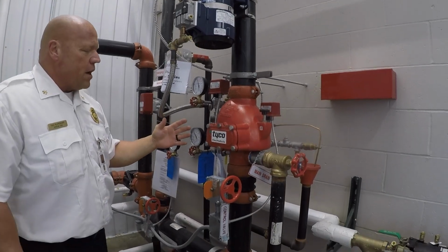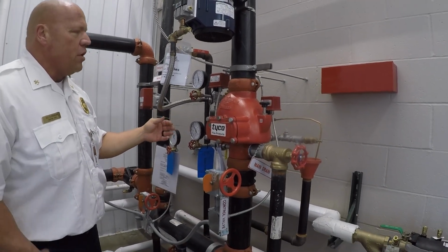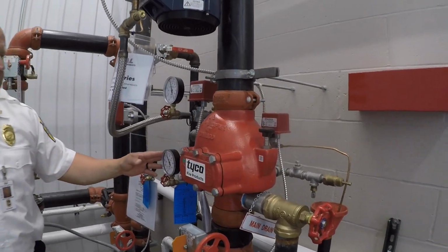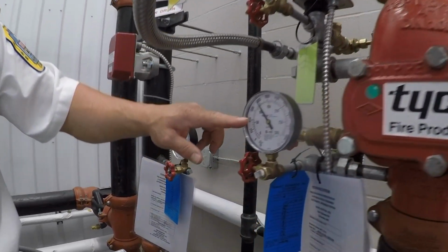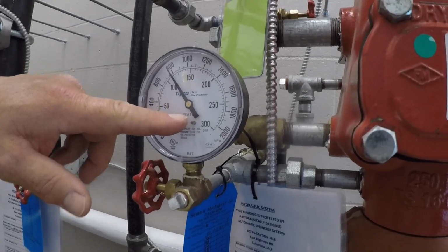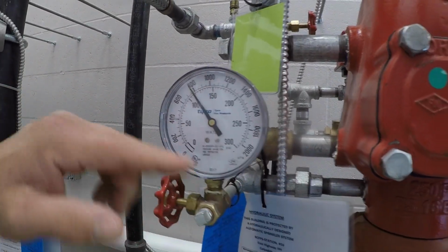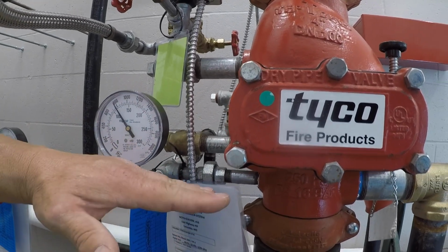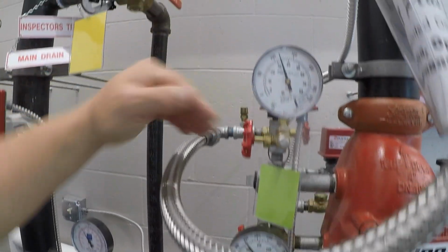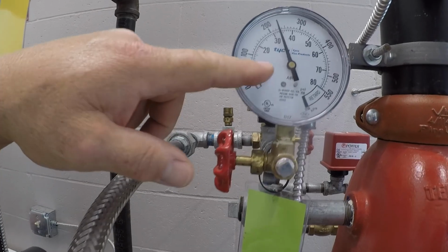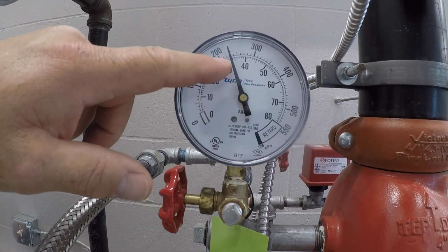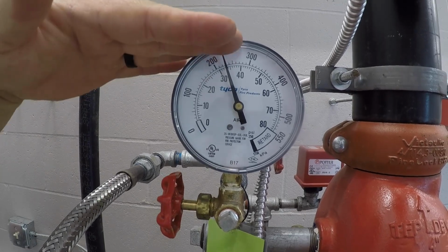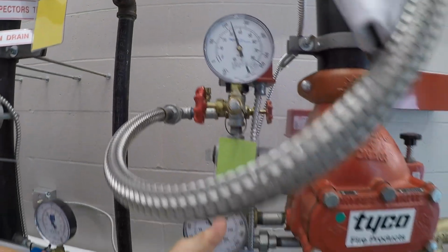Two things about a dry pipe system that you need to know whether it's activated or not. If you look at the water pressure side of this, you have a water gauge, and it says water, and it's below this pipe. And you've got about 110 pounds of pressure on this water line coming in. If you look above this valve, you have the air pressure, which is about 34 pounds of air. So you have 34 pounds of air holding back 100 pounds of water.